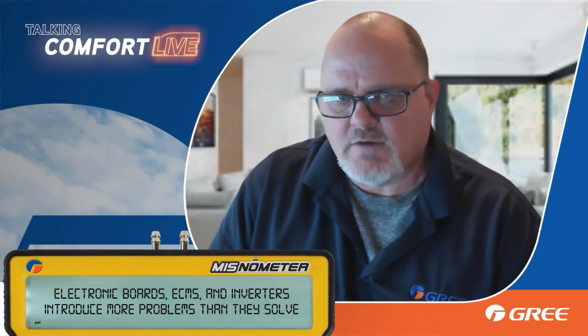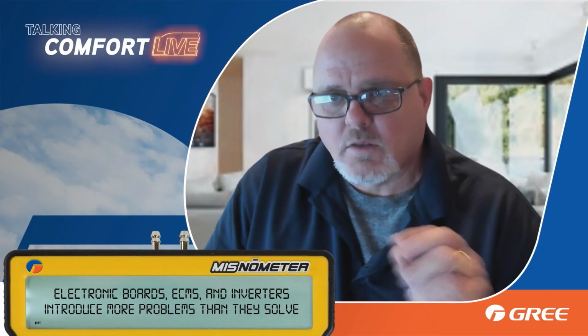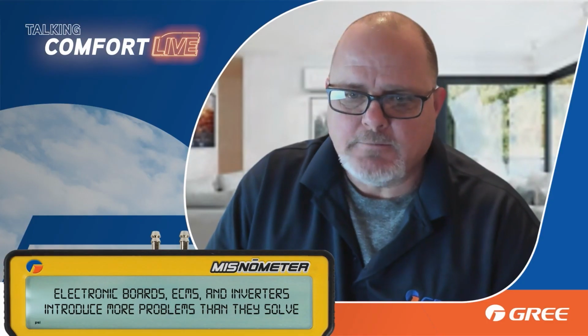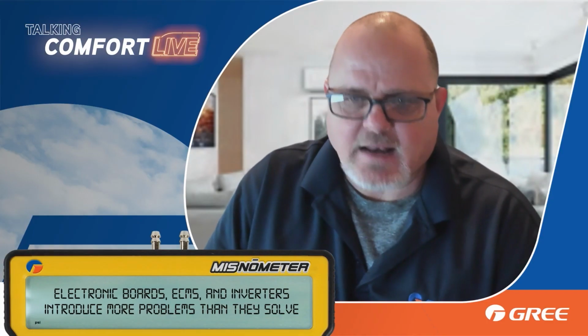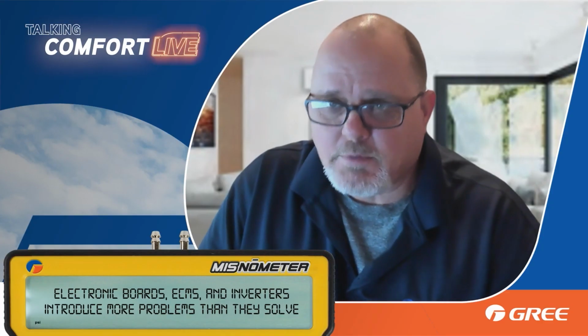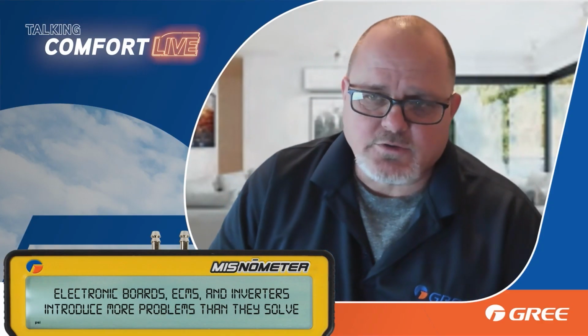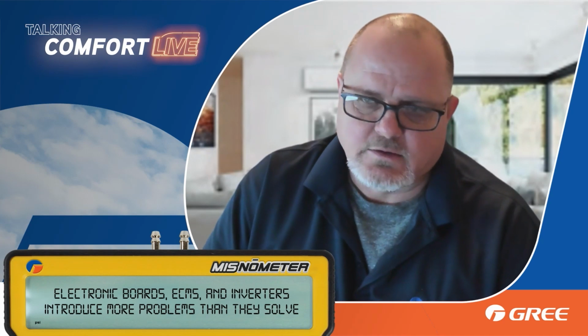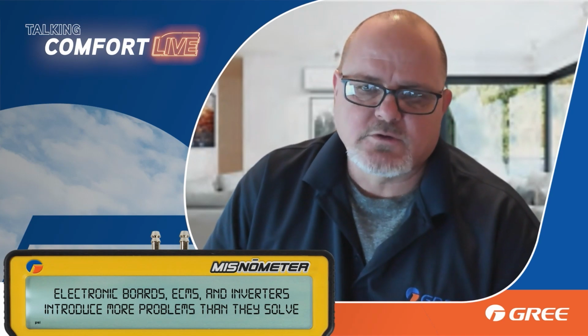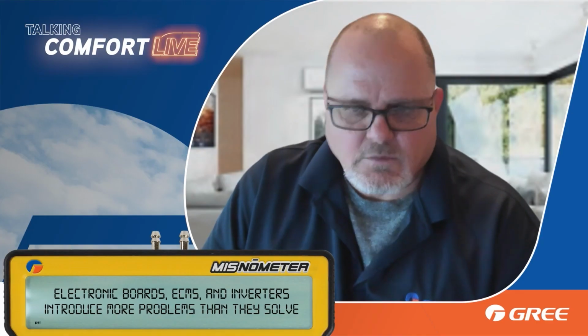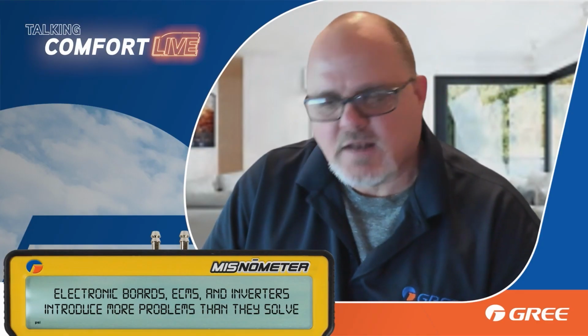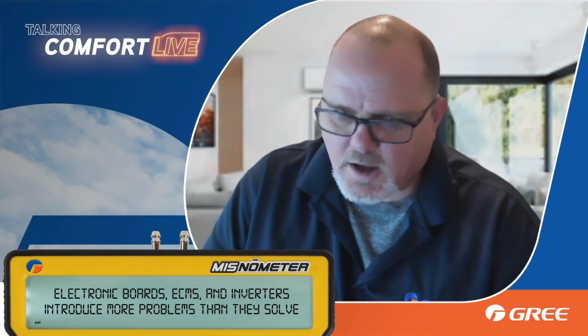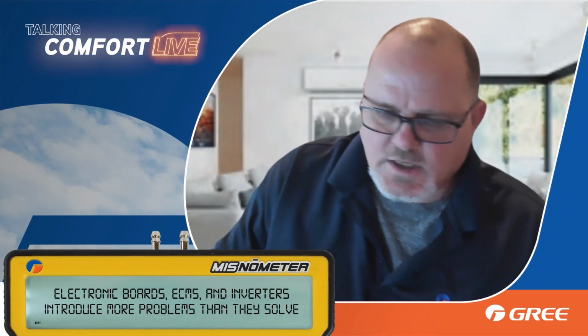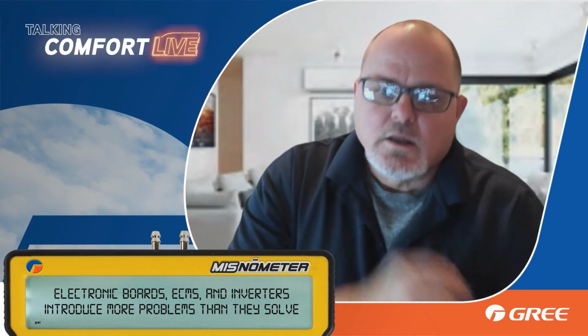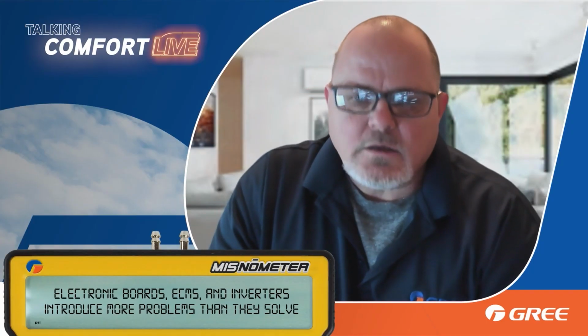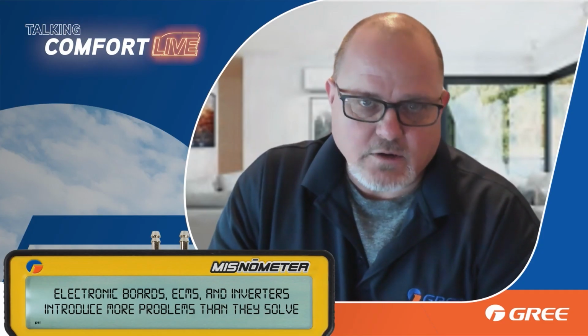So if you have a piece of data, in other words, say a thermistor that's not reading properly, the board's getting bad data. So the machine's not going to run properly. It can't be electrically shorted or open. You have an error code for that. But you can very much have a thermistor out of range that is causing an erratic operation. It doesn't happen that often. These thermistors are very reliable. It ain't like we're constantly changing thermistors. I don't think that's it at all. But you can have that one that is giving you erroneous errors.